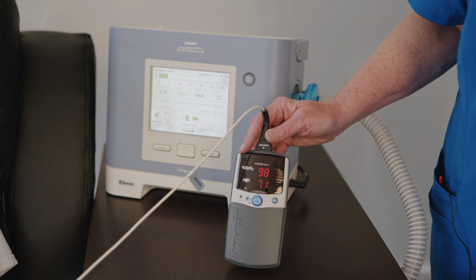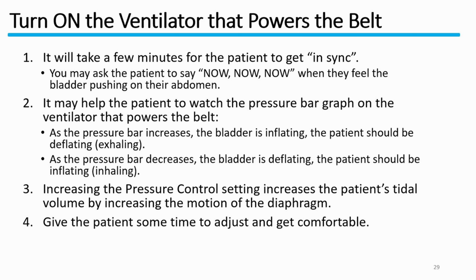The patient should be deflating or exhaling. As the pressure bar decreases, the bladder is deflating. The patient should be inflating or inhaling. Increasing the pressure control setting increases the patient's tidal volume by increasing the motion of the diaphragm. Give the patient some time to adjust and get comfortable.